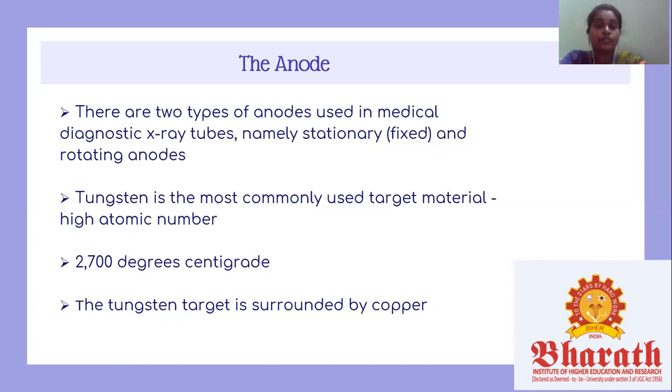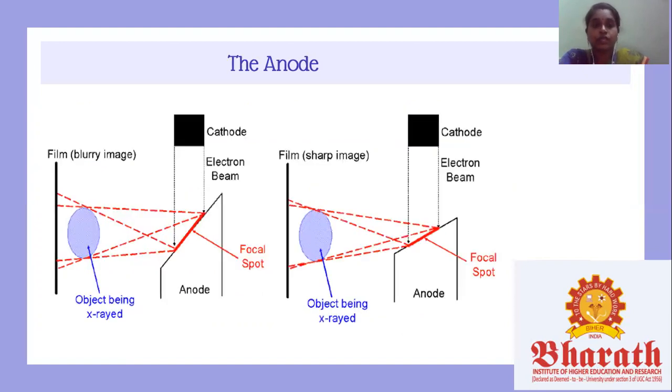The area over which the electrons from the cathode strike the anode is referred to as the focal spot. The cooler the anode can be kept, the smaller the focal spot can be, and the greater the image detail is possible. If a high X-ray output is required, a large focal spot could be needed to mitigate the temperature increases. In early tubes, the angle of the target was usually 45 degrees. We can check with the diagram.